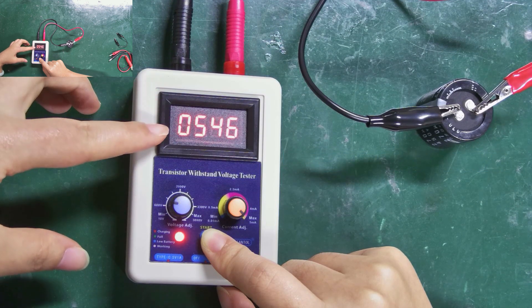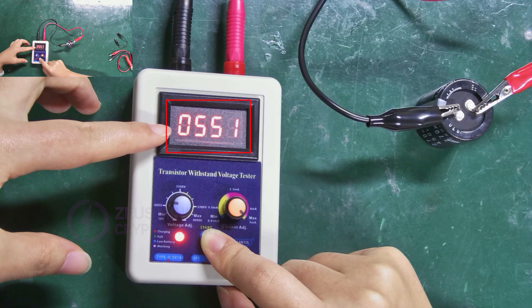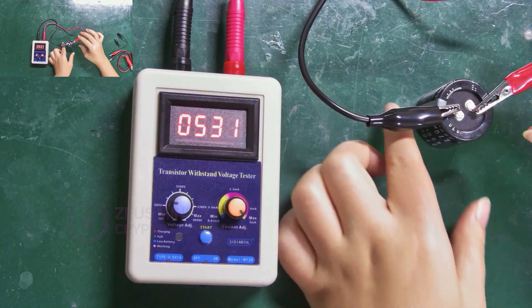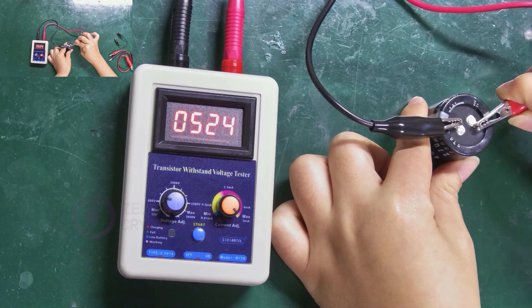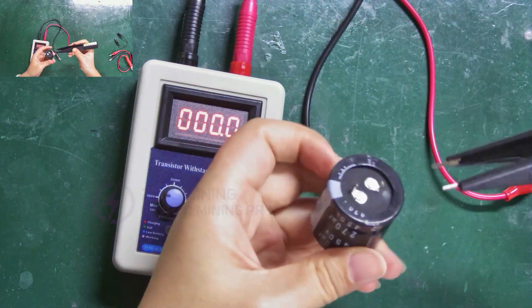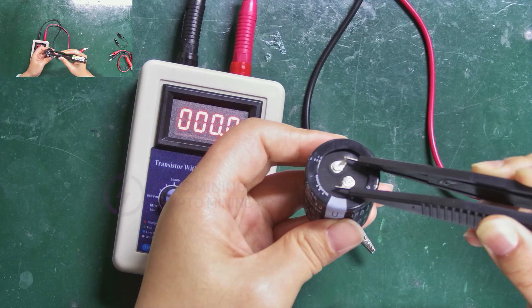Okay, this is its withstand voltage value, which is around 550 volts. When removing the clips, take off the positive one first, then the negative one. After that, discharge the capacitor.